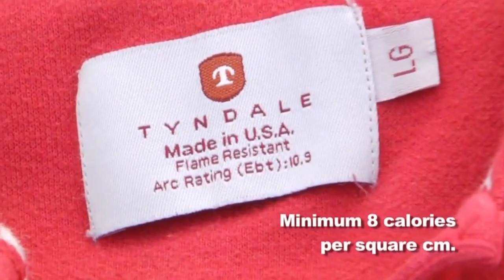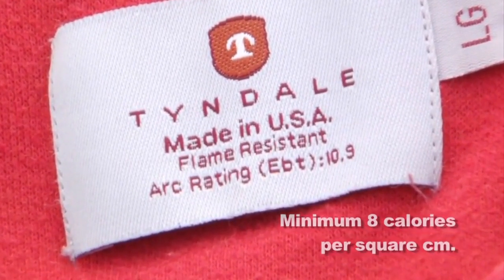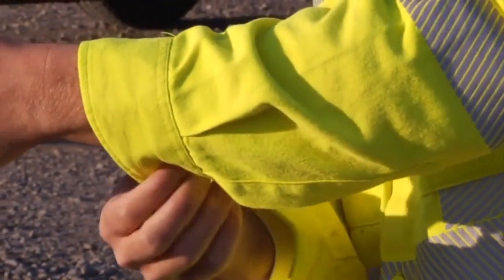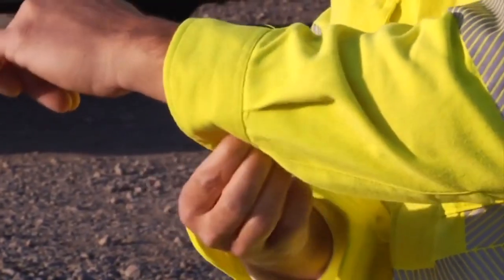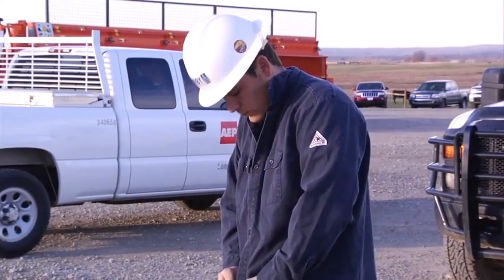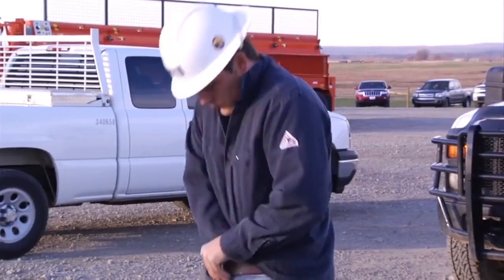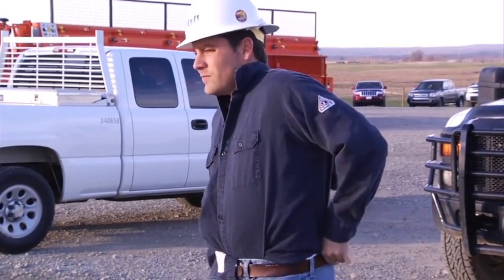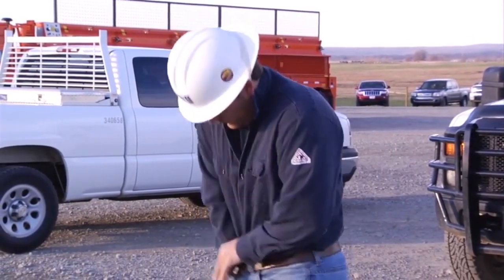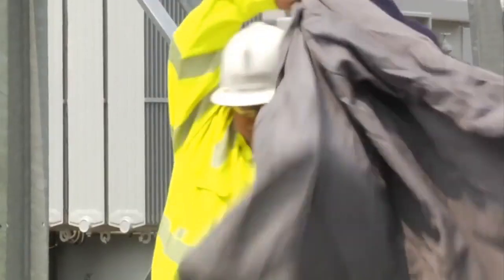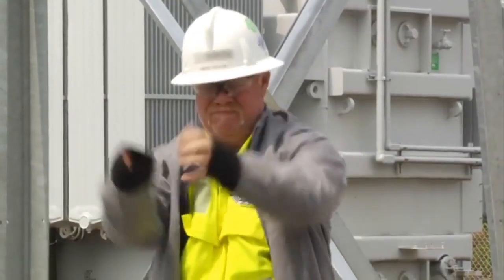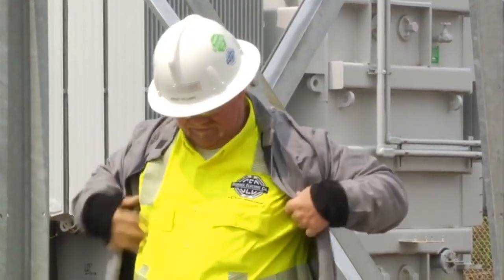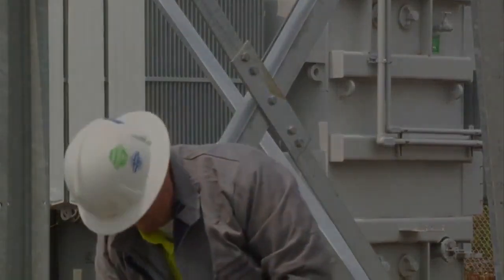Arc flash clothing shall, at a minimum, meet an arc rating of 8 calories per square centimeter. All outer layers for the upper and lower body shall have the appropriate arc flash rating. When a shirt is worn as the outer layer, it shall be long sleeves. Sleeves shall be rolled down and buttoned with the shirt tails tucked into the trousers. When an additional layer is required, such as a coat or overalls, it also shall have the appropriate arc flash rating.